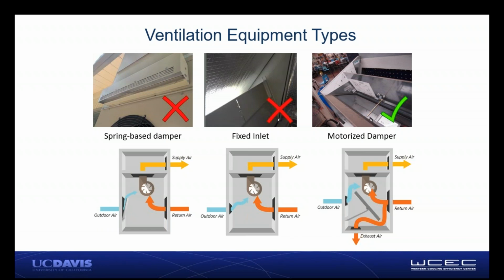You might have issues with the doors, and the fan won't even be able to move that much air because of the pressure difference. So really the most simple system that will work is a motorized damper, and I show this damper up here in a Bard wall mount unit. Basically the damper opens and closes: when the system turns on, the damper opens, the ventilation air comes in, and then it exhausts the air as well.